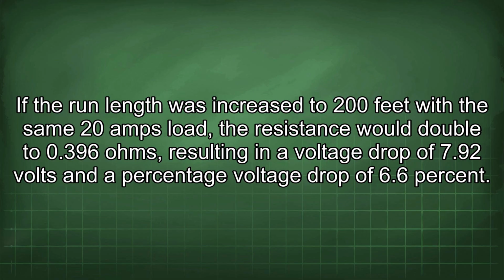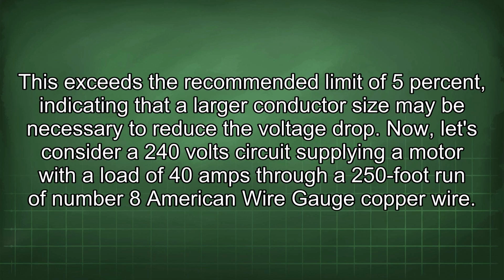If the run length was increased to 200 feet with the same 20 amps load, the resistance would double to 0.396 ohms, resulting in a voltage drop of 7.92 volts and a percentage voltage drop of 6.6%. This exceeds the recommended limit of 5%, indicating that a larger conductor size may be necessary to reduce the voltage drop. Now let's consider a 240-volt circuit supplying a motor with a load of 40 amps through a 250-foot run of number 8 American wire gauge copper wire.